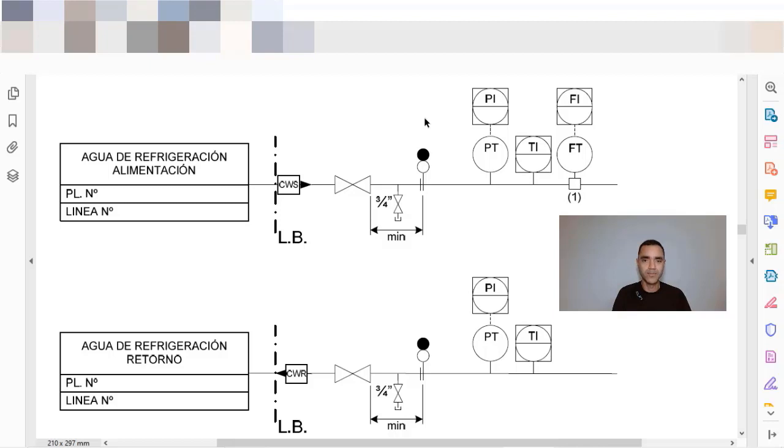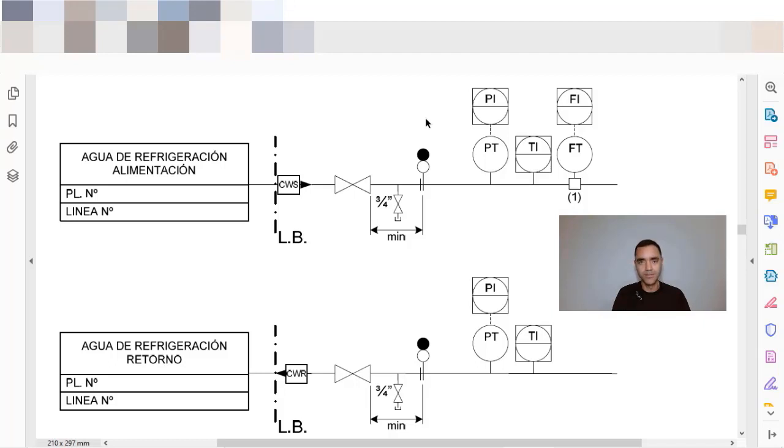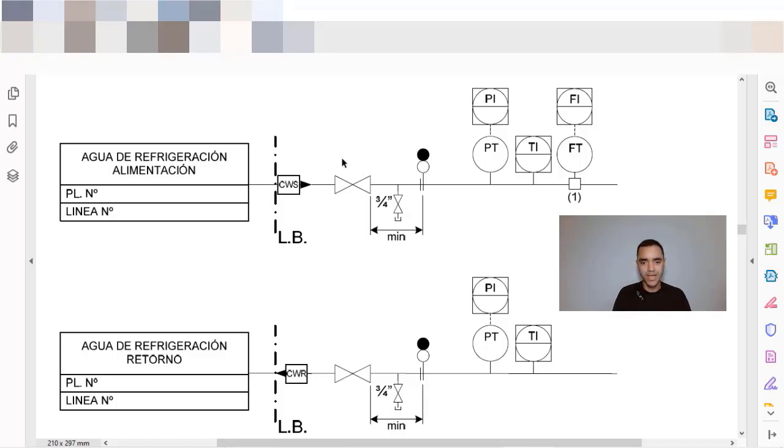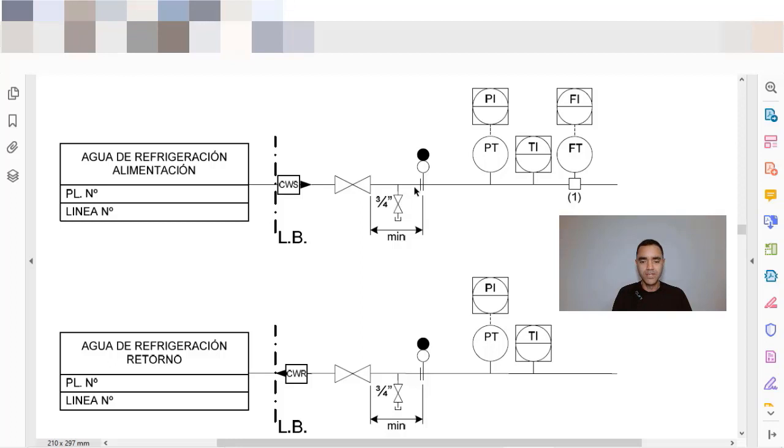Most often you have the nominal pipe size of the line, you have the fluid, you have the number of the units, you have the sequential number of the line, you have the material of the pipeline. In some cases, if you have insulation, you also add that to the pipe numbering.